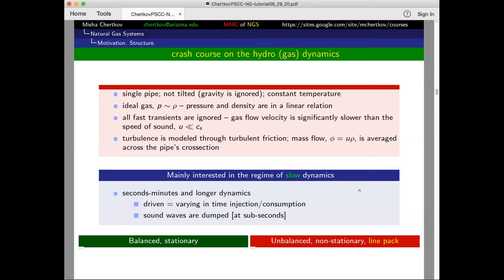A very significant difference between power systems and gas systems is in how you need to model. Even in the slow regime, the gas system is never in balance. In a power system, on a scale of a minute or even seconds, we are in balance — whatever we inject, the same amount we consume. But in a gas system you can pack gas: you can literally inject gas and not withdraw it, or the other way around. This is called line pack. Pressure variations are also much more significant than voltage variations in a power system — pressure may change on the order of 300 PSI to 800 PSI easily, basically a factor of two.